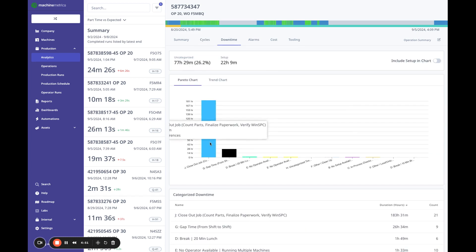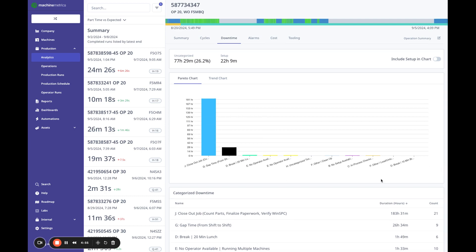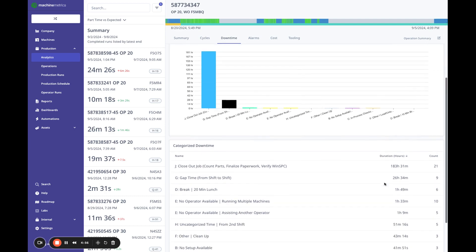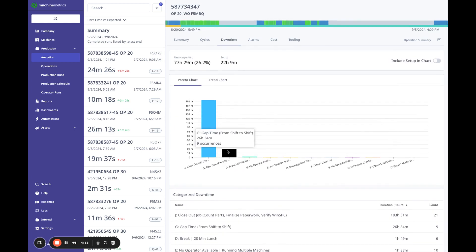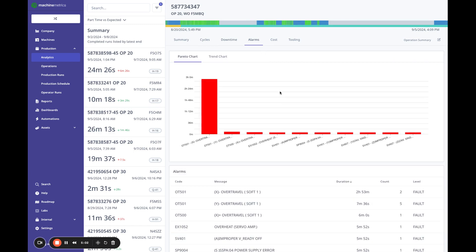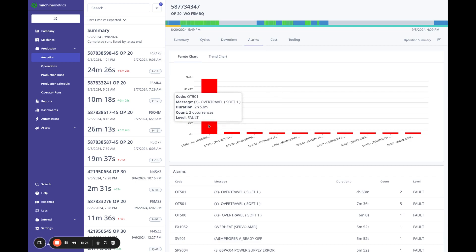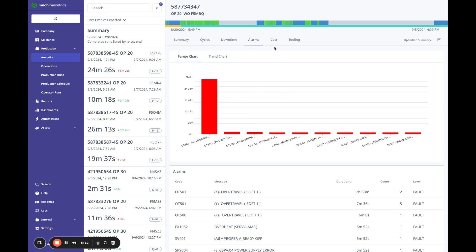So moving on, we have the ability to look at our downtime Pareto. So I can see where the downtimes are coming from. This would be either manually entered in or automated through auto downtime. But also we can view our alarms. So I see I have an over travel alarm, looks like about three hours here. That's my biggest offender. That might be part of my downtime issues.